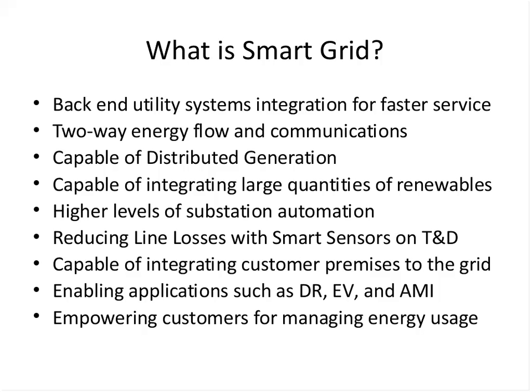This requires a certain level of automation in the substation. That's why protocols for substation automation are so important now, so that every granular attribute of every device is represented in the SCADA system. You also need high-speed networks to communicate and deal with things that are very time-sensitive, sometimes on the order of 4 milliseconds for certain protective relays, for instance.